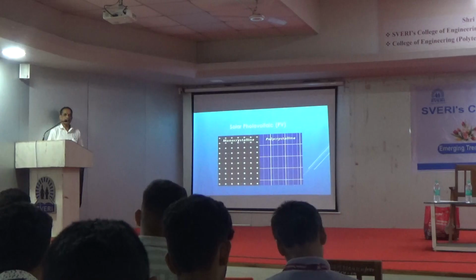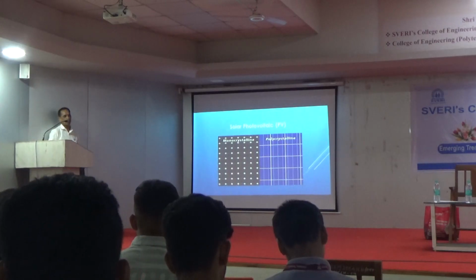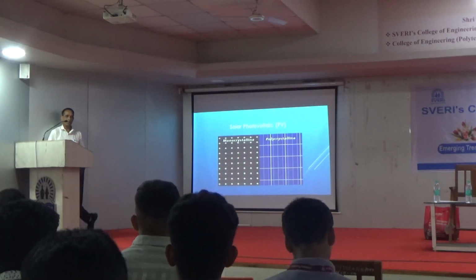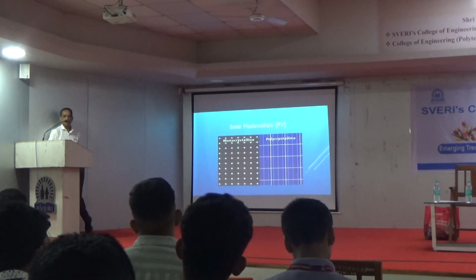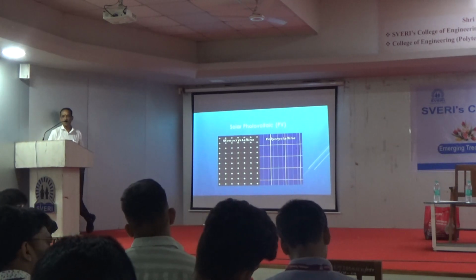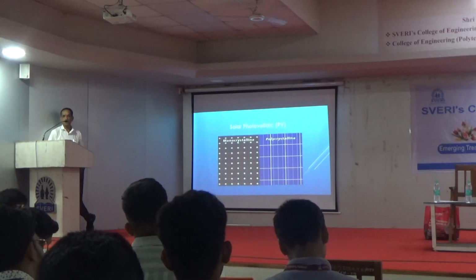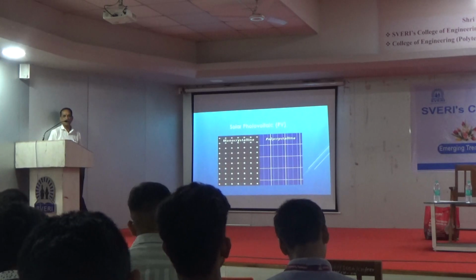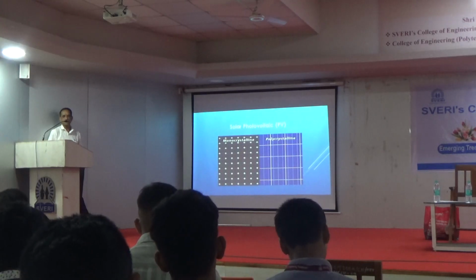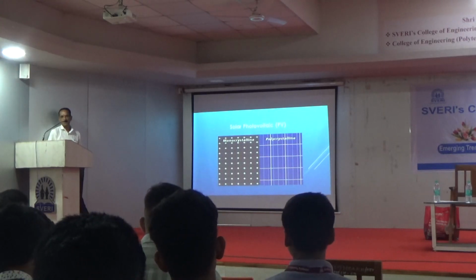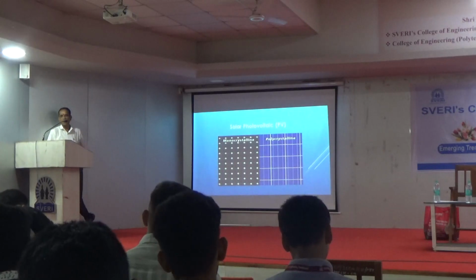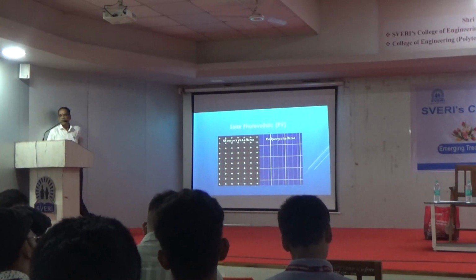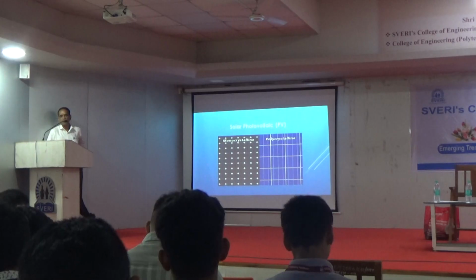Now for our business, like 1 kilowatt, 2 kilowatt or 3 kilowatt grid tie, the panels available are 500 watt minimum. The voltage for our grid tie is 48 to 50 volts, 500 watt. Then next is 550 watt. In between, 535 is available. The latest launch is 740 watt in 50 volt.